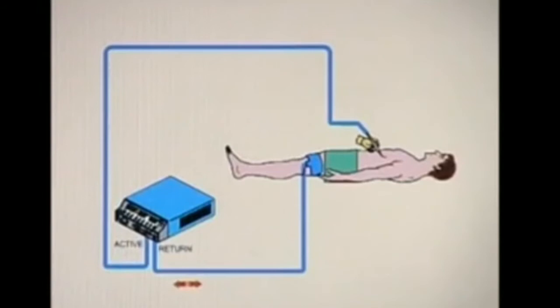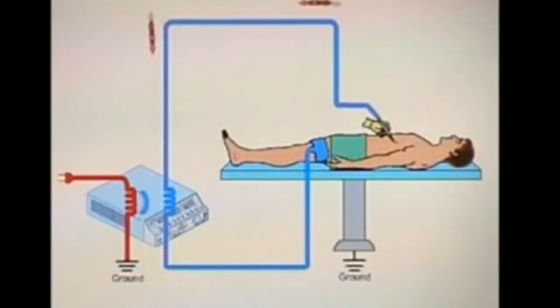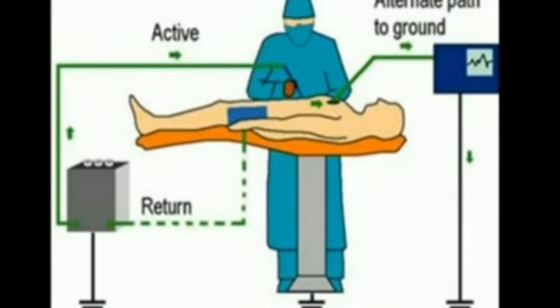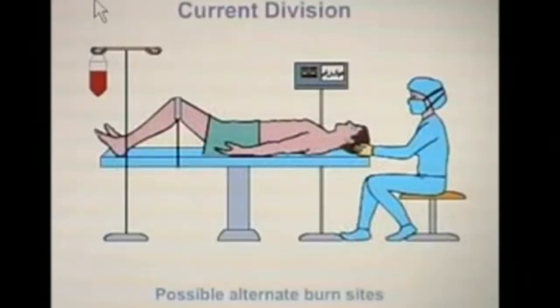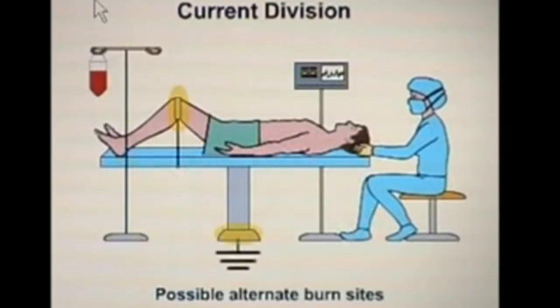Most electrosurgical generators in the UK are what is termed isolated. However, if the system you are using is not an isolated one, you must take special care to ensure the patient return electrode is properly applied and checked throughout the operation. The major potential hazard with the older style of grounded generators is that the current flowing through the patient will not preferentially look for the patient return electrode to complete the circuit. It is equally happy to flow back to earth. Therefore, should the patient return electrode become detached from the skin, the current may leave the body by any number of routes, for example, the operating table or ECG electrodes, causing burns at these points due to current concentration.